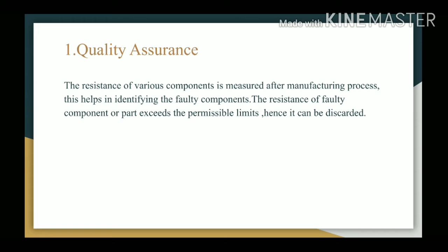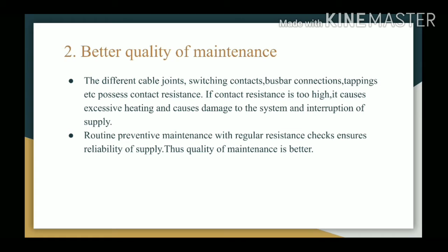Second is better quality of maintenance. The different cable joints, switching contacts, busbar connections, tappings, etc. possess contact resistance. If contact resistance is too high, it causes excessive heating and causes damage to the system and interruption of supply. Routine preventive maintenance with regular resistance checks ensures reliability of supply, thus quality of maintenance is better.